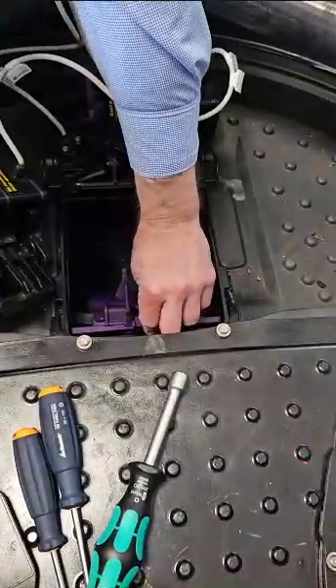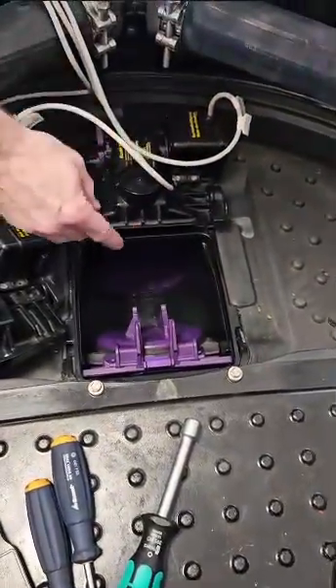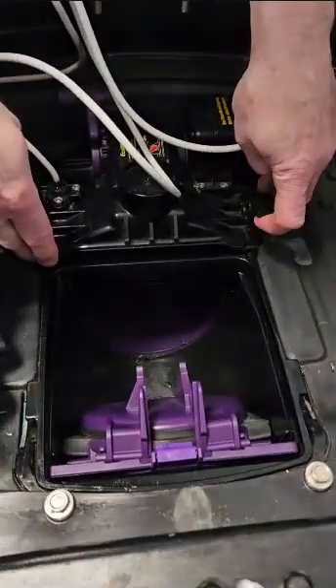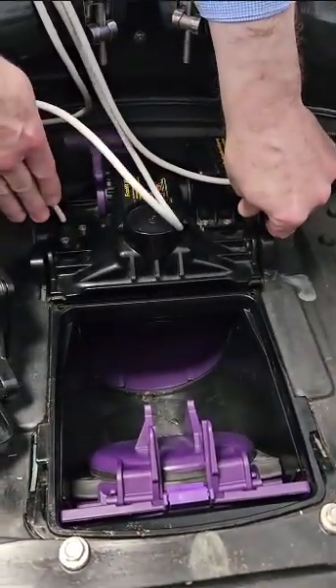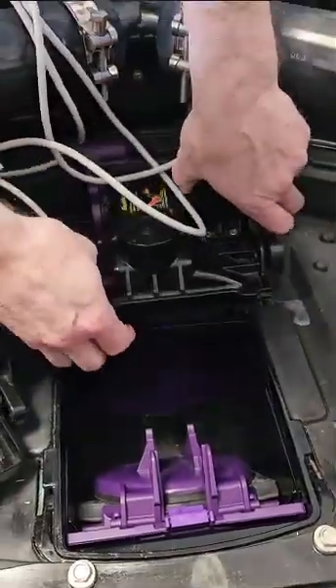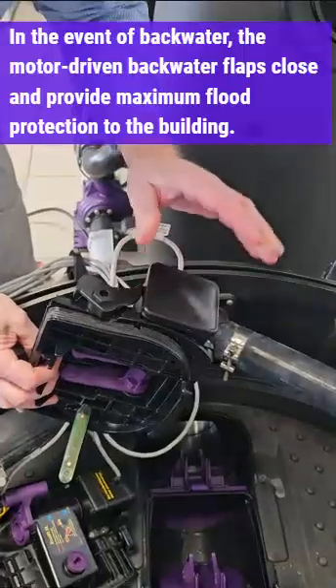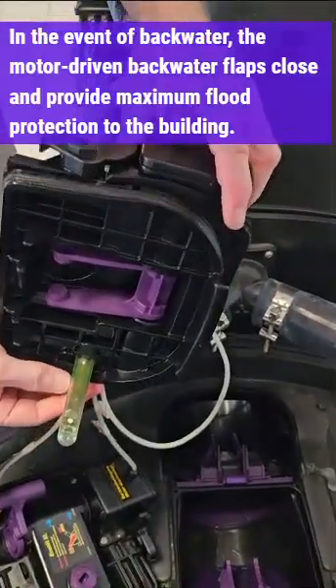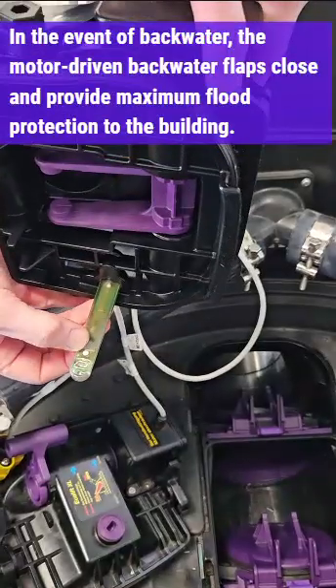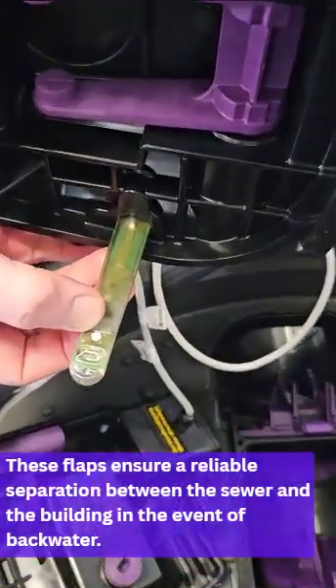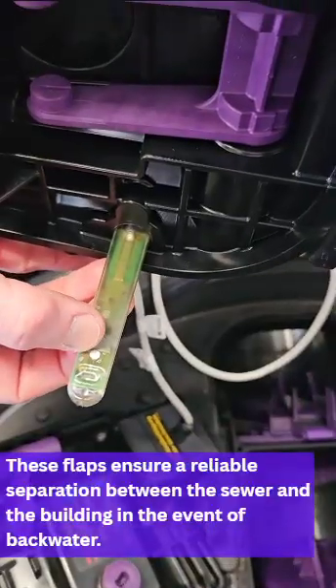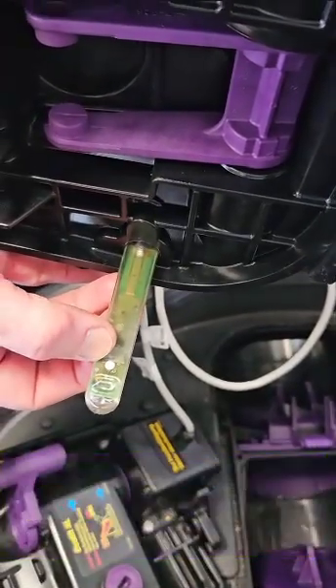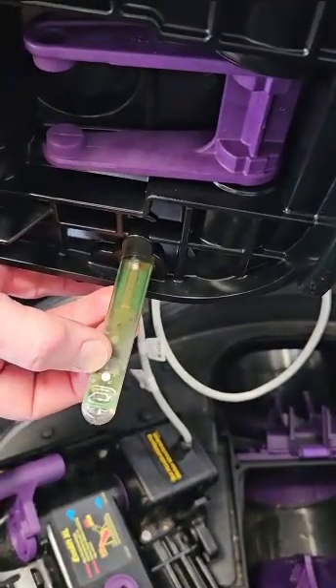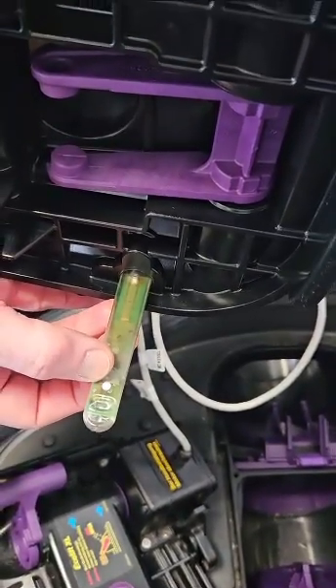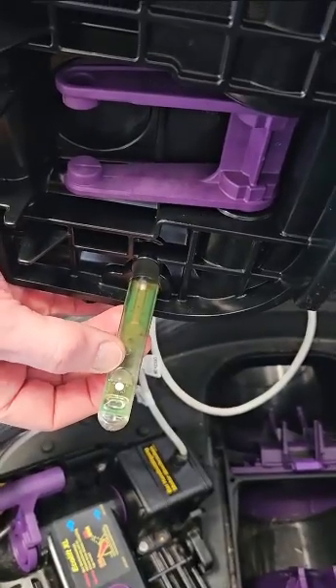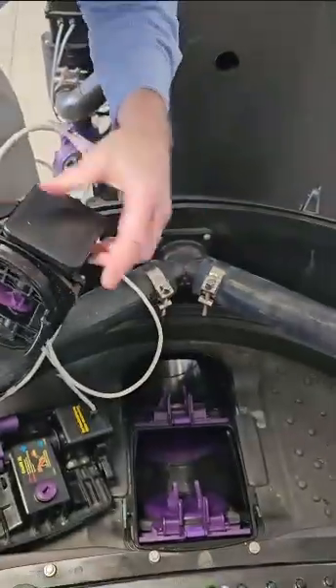This motor is controlling this flap. There's a clip holding this flap in place that can be removed. This backwater flap should be removed, as well as the housing. This is very easy to do without any tools. This should go through a quick visual check. Any debris should be removed. The gaskets, this is a 2K gasket, so it can't be misplaced or lost. If it is damaged or there have been rodents or rats gnawing on it, eating on it, this should be replaced. But all the gaskets should be visibly inspected and cleaned to make sure they're in proper working condition.